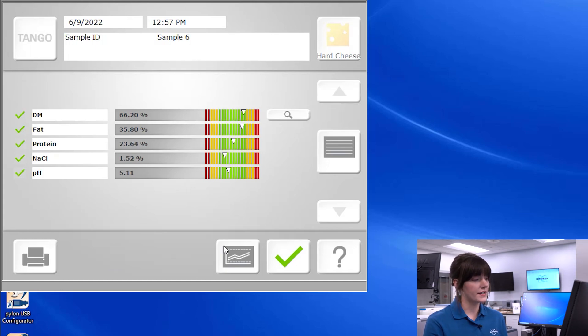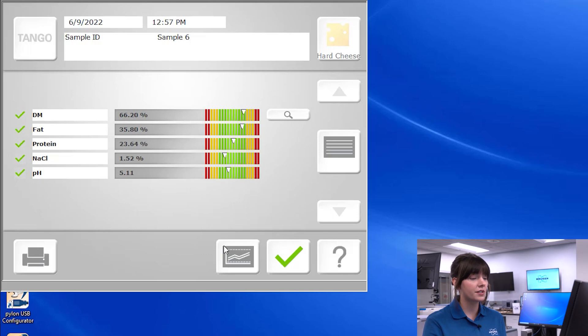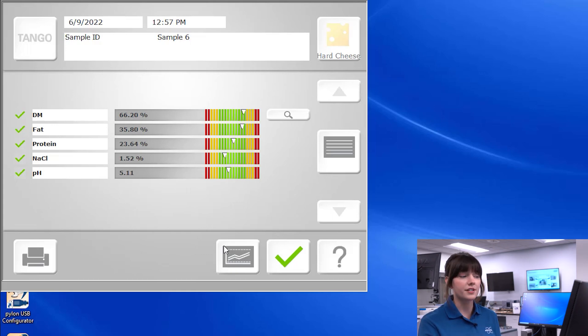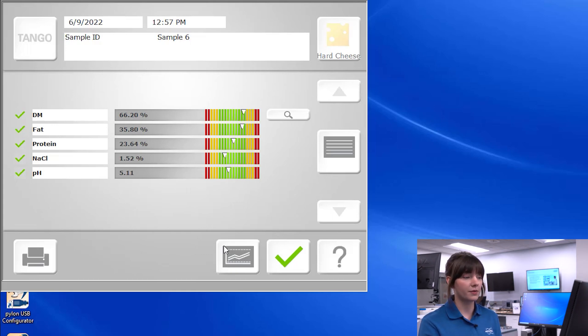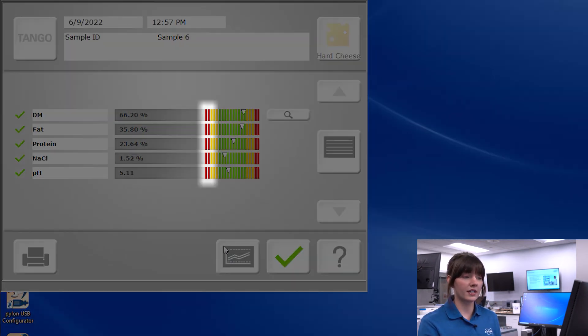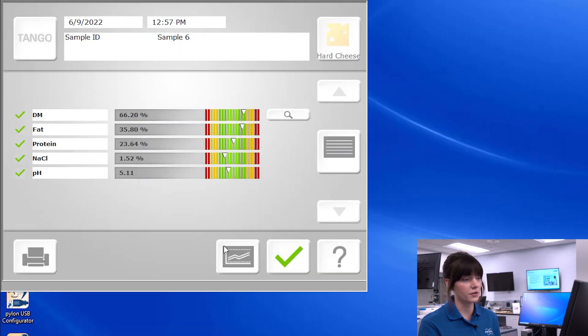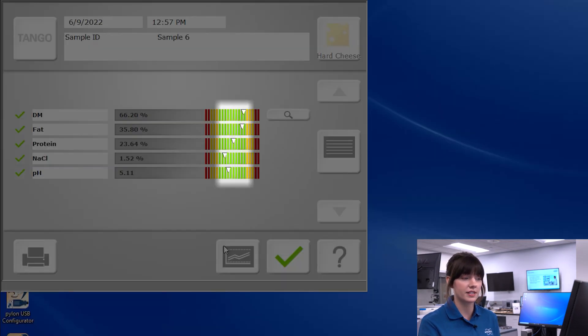After about 45 seconds, we're presented with the evaluation results. This screen provides you with both numerical values as well as visual indicators of where your results lie. In your setup screen, you're able to define limits. Red depicts what's out of tolerance, yellow indicates your cautionary limits, and green indicates what is acceptable.